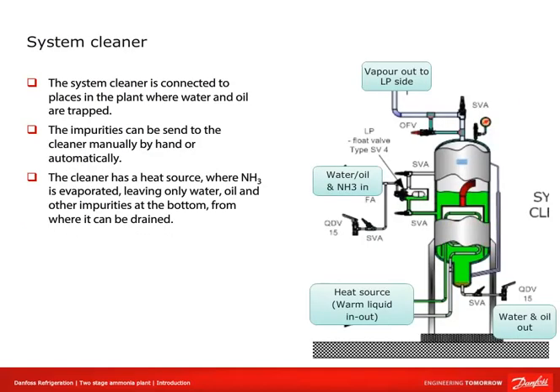The system cleaner is connected to places in the plant where water and oil are trapped. Impurities can be set for cleaning manually or automatically. The cleaner has a heat source where ammonia is evaporated, leaving only water, oil, and other impurities at the bottom from where they can be drained.